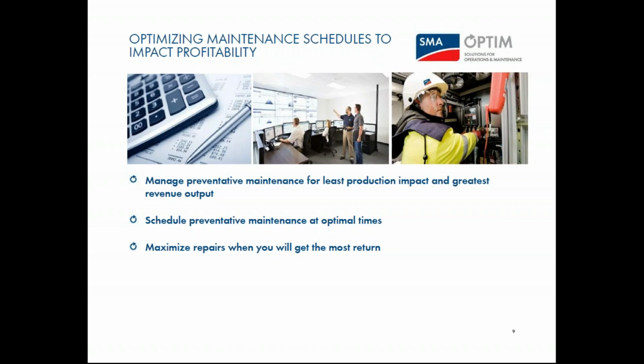Preventive maintenance schedules typically are conducted on a calendar schedule per manufacturer's requirements to maintain warranty coverage. If you know summer months are coming and stresses will increase on the inverter or other plant components, you could do a minor preventative maintenance cycle on only the fans and filters. That way we can ensure the inverters are ready for the higher production months ahead and ideally reduce downtimes when you're making the most money out of your plant.